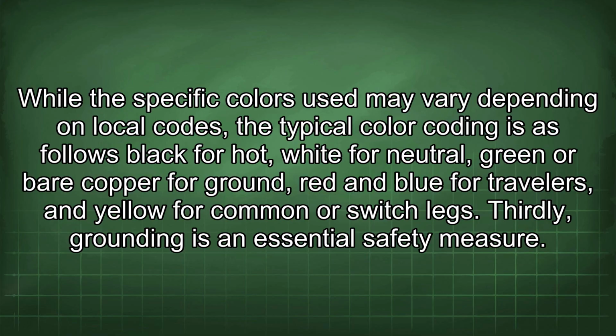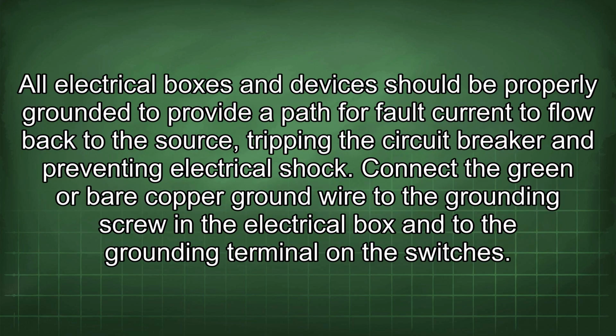Thirdly, grounding is an essential safety measure. All electrical boxes and devices should be properly grounded to provide a path for fault current to flow back to the source, tripping the circuit breaker and preventing electrical shock. Connect the green or bare copper ground wire to the grounding screw in the electrical box and to the grounding terminal on the switches.